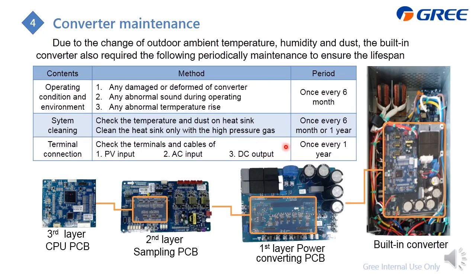As for the system cleaning, just focus on the temperature and the dust on the heat sink to ensure it can release enough heat and avoid overheating. Also clean the heat sink with high pressure gas. And for the terminals, we recommend to check them every 1 year, including the PV input, AC input, and DC output if you have upload to the grid power supply.